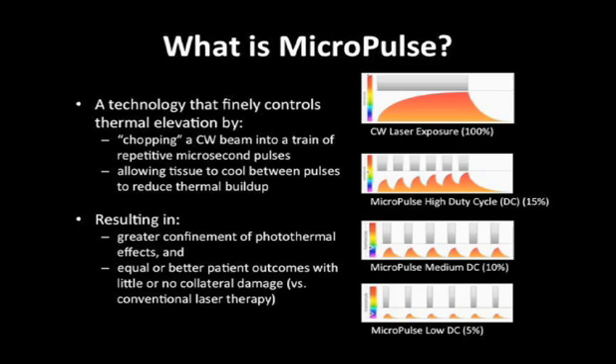The idea is to use the advantages of conventional laser therapy — i.e., continuous wave — and break up that continuous wave into very small, discrete micropulses. This allows energy to be delivered with a cooling period in between, reducing thermal buildup. Essentially, this allows the tissue to cool and prevents collateral damage.